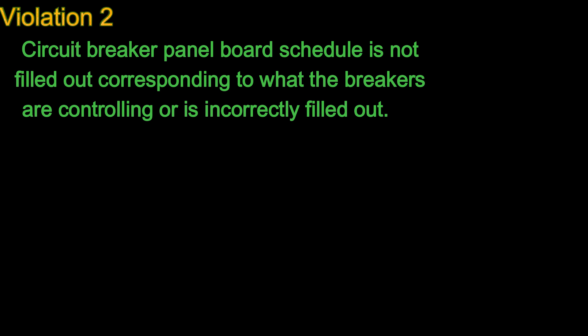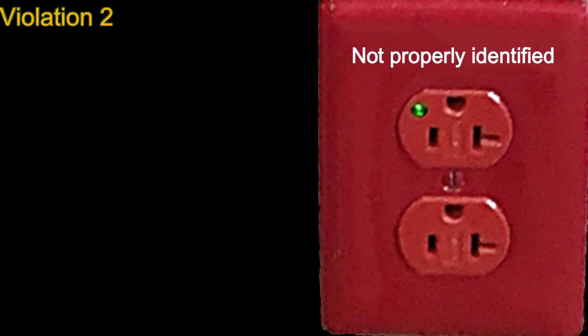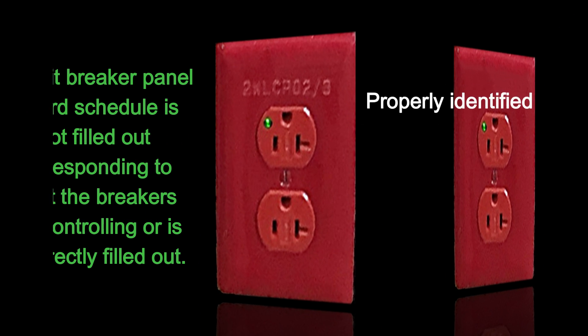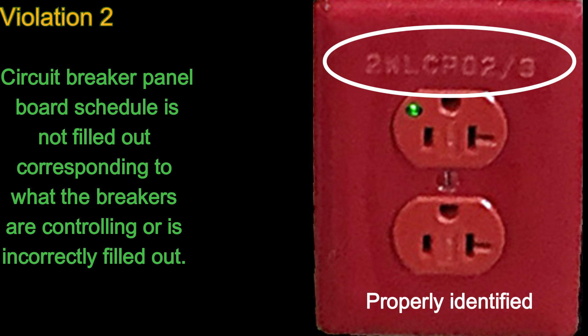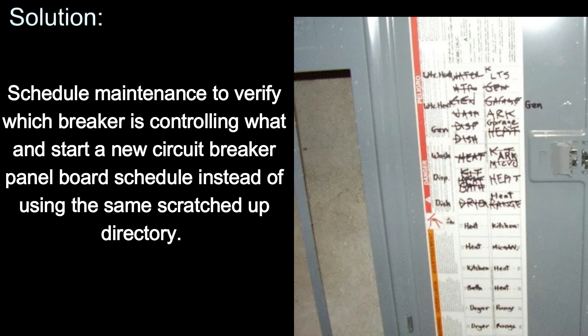Number 2: Circuit breaker panel board schedule is not filled out corresponding to what the breakers are controlling, or is incorrectly filled out. Code NFPA 70 408.4, field identification required, states every circuit and circuit modification shall be legibly identified as to its clear, evident, and specific purpose or use, located on the face or placed inside of the panel door. Solution: Schedule maintenance to verify which breaker is controlling what, and start a new circuit breaker panel board schedule instead of using the same scratched-up directory.